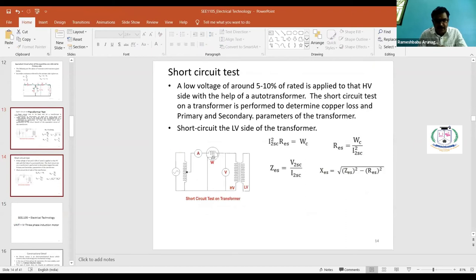the short circuit test. Why are we performing the short circuit test? To find the copper loss of the machine as well as the other parameters R1, X1, R2, X2. To determine these values, we perform the short circuit test. We apply only 5 to 10% of the rated voltage to the high voltage winding.